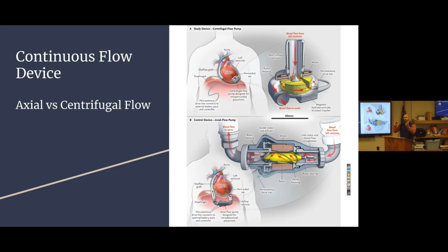But essentially all of these devices now work by continuous flow, so they're non-pulsatile. It's either by axial flow or centrifugal flow. The slightly older ones are the centrifugal flow pump, or the axial flow pump on the bottom. The newer generations that are coming out are just using centrifugal flow. Essentially it's a magnet that's spinning, and it creates a suction effect, so blood is pushed through and can go from the LV to the aorta. Simple as I can make it.